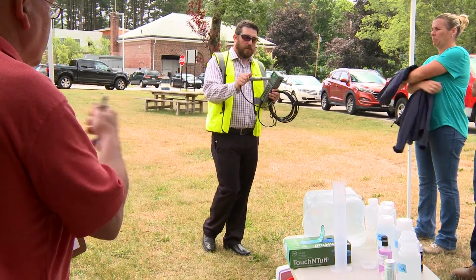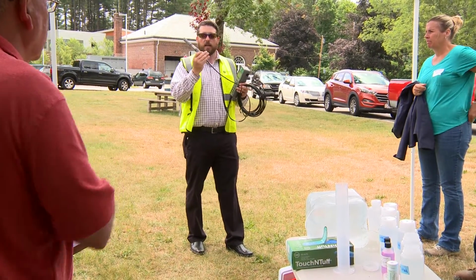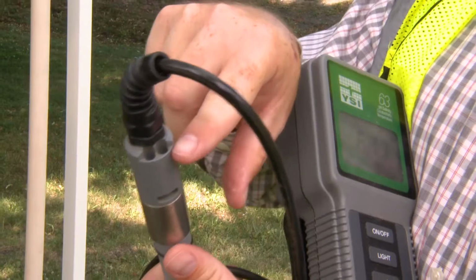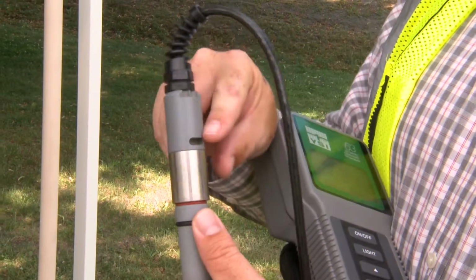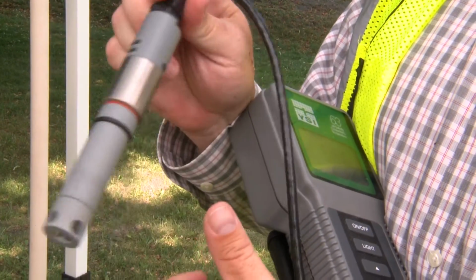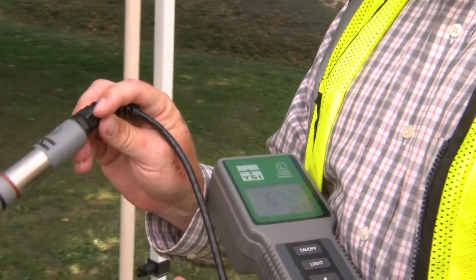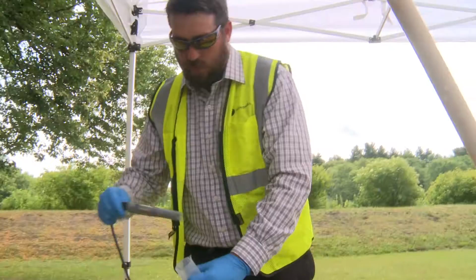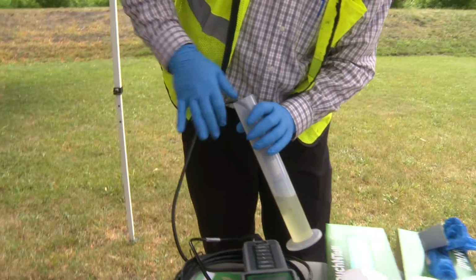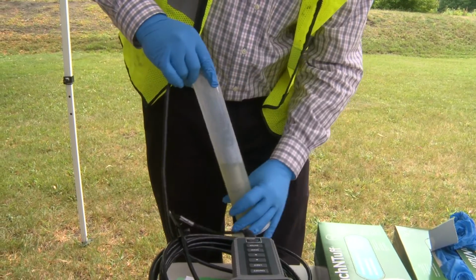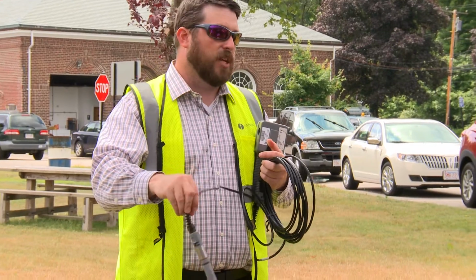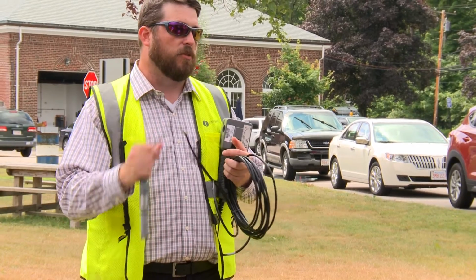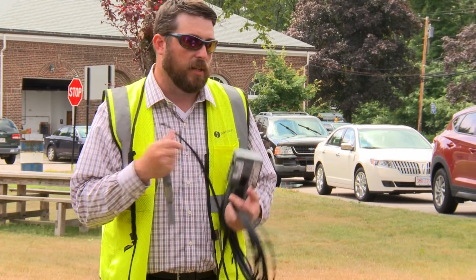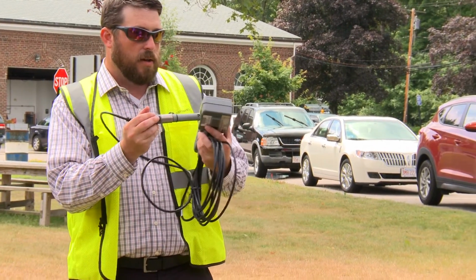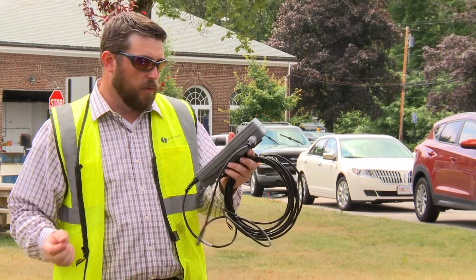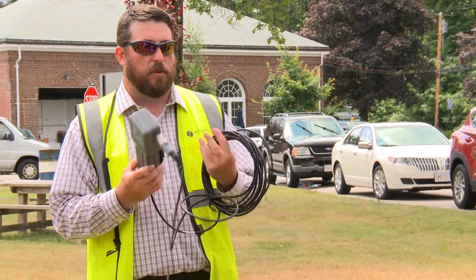On this unit, for conductivity and salinity, you can see the two holes sort of at the top of the meter, and then this other hole, the water is supposed to flow through, and the sensor is actually internal in here. So when you dip this in your sample bottle, all those holes need to be submerged, and you also want to agitate the water a little bit to get that water flowing through the cell to get a consistent reading of what the conductivity or salinity are in your water body or sample of interest.